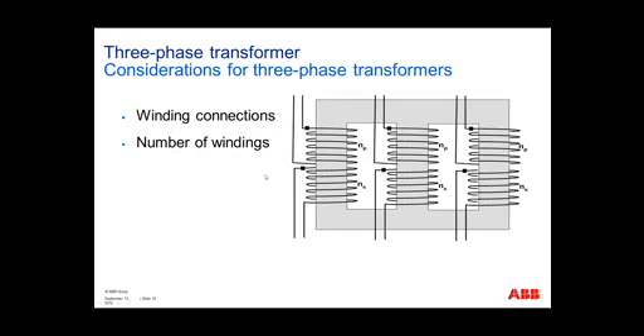Showing the model of a three-phase transformer. Considerations of a three-phase transformer. What you're looking at is a two-winding, three-phase transformer. Excuse me. NP is representing the windings associated to the high side voltage, and NS is the windings associated to the low side voltage. On the leftmost leg will be A phase, B phase, and C phase on the high side. On the low side, you'll have A phase, B phase, and C phase.